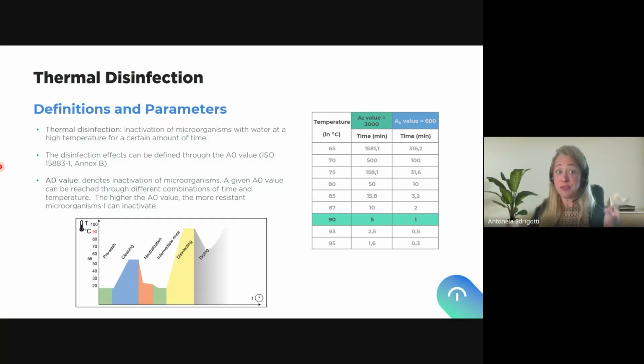Okay? The disinfection effects, or these two parameters, are defined through the A0 value, which is also defined in the ISO 15883 Part 1 standard. The A0 value will denote the level of inactivation. So this is just the parameter we need to know to understand the level of disinfection we reach with our washer disinfector. Okay, it does not just matter the time and the temperature, because different manufacturers can work with different combinations, but in the end different combinations of time and temperature can reach the same A0 value.